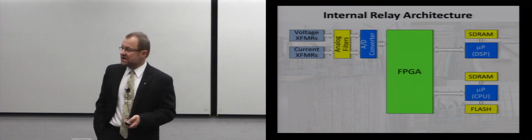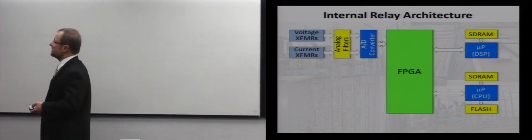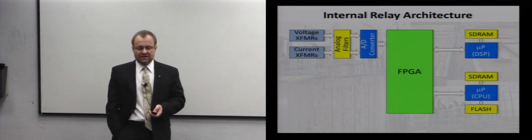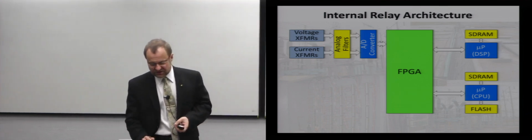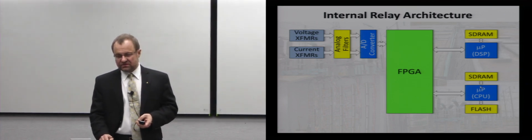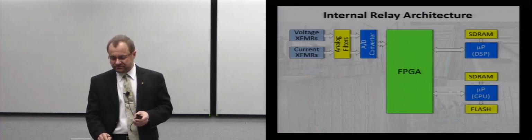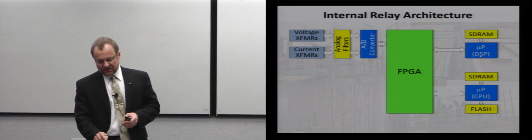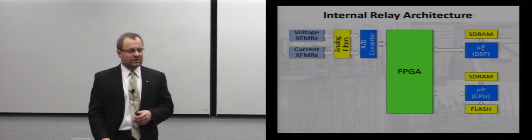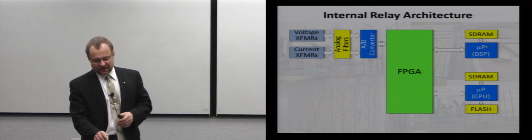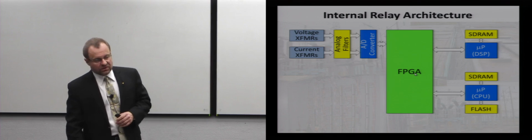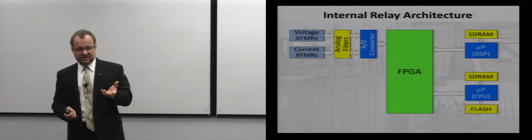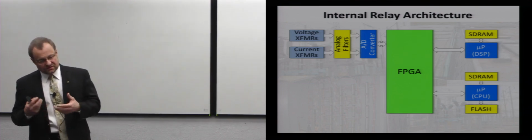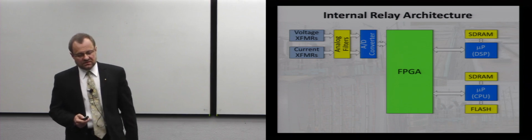The next thing is I may have DSP-like microprocessors for just data crunching. Some stuff is more suited to a CPU. So for example, what I could mean by CPU is I could run communication protocols, I could run HMI, I could run stuff that is relatively high level and relatively slow. And when I'm calculating magnitudes and operating equations, and I have to run it at the rate of once a millisecond, I will apply a separate DSP-like environment and do it maybe on the FPGA. Right now, what the new parts allow us, we have the quad microprocessor, where they have four cores inside and they're optimized. So this is a new way to maybe optimize the internal architecture of the relay.